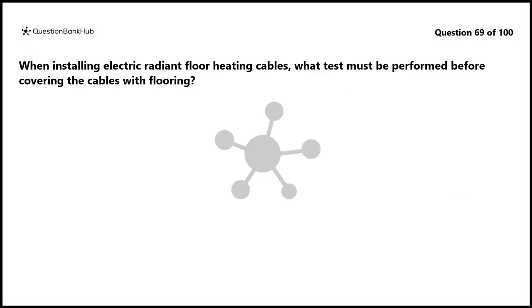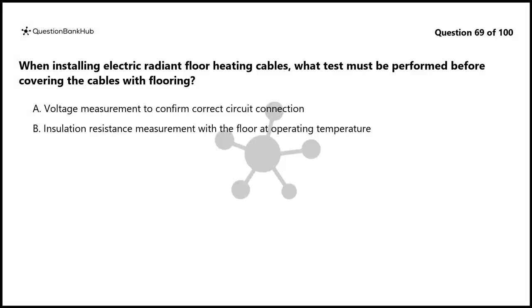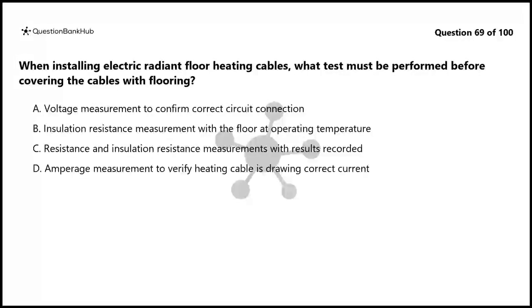Question 69. When installing electric radiant floor heating cables, what test must be performed before covering the cables with flooring? A. Voltage measurement to confirm correct circuit connection. B. Insulation resistance measurement with the floor at operating temperature. C. Resistance and insulation resistance measurements with results recorded. D. Amperage measurement to verify heating cable is drawing correct current.